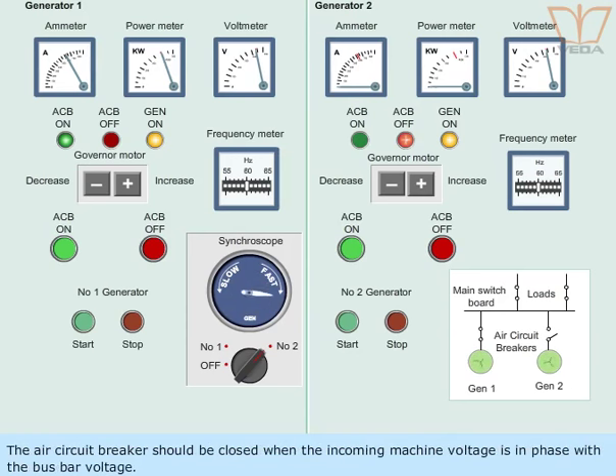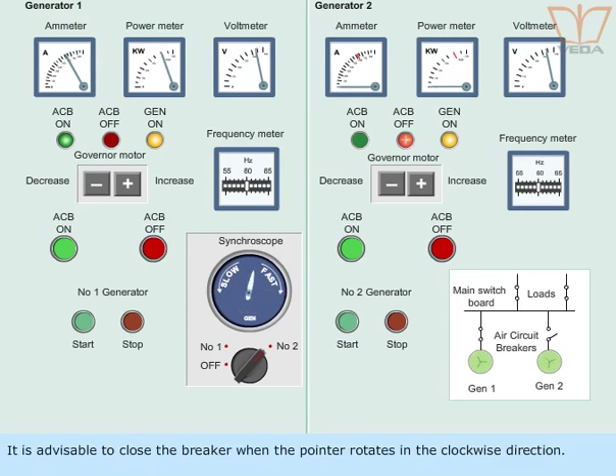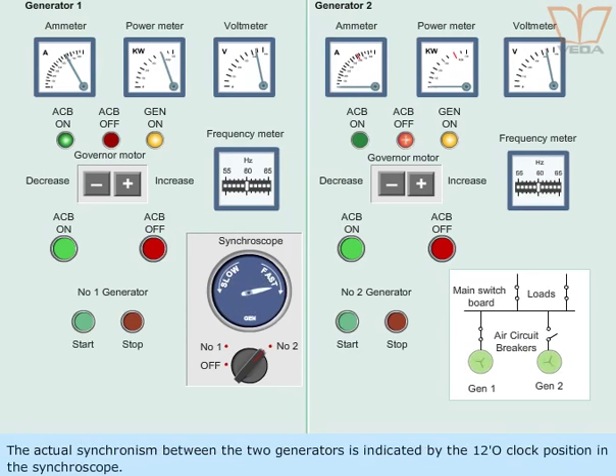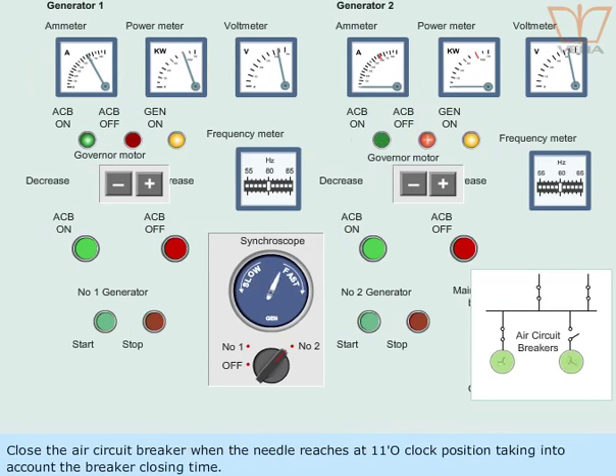The air circuit breaker should be closed when the incoming machine voltage is in phase with the bus bar voltage. It is advisable to close the breaker when the pointer rotates in clockwise direction. The actual synchronism between the two generators is indicated by the 12 o'clock position in the synchroscope. Close the air circuit breaker when the needle reaches at 11 o'clock position, taking into account the breaker closing time.